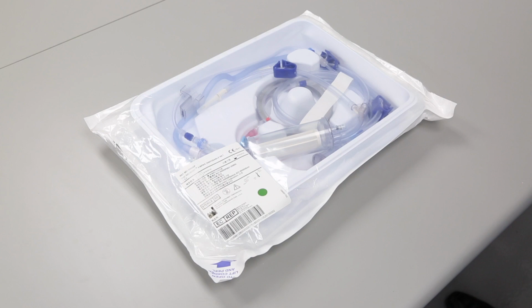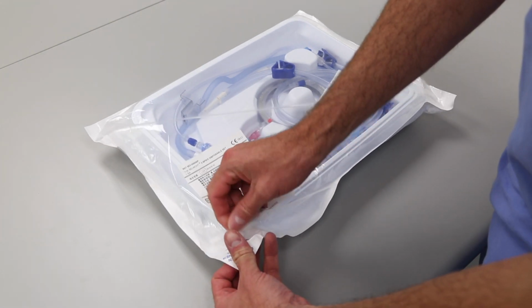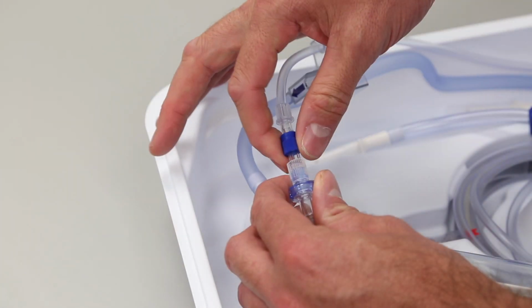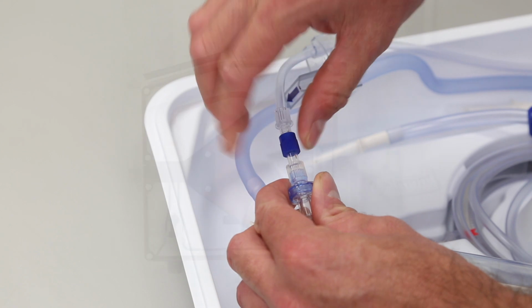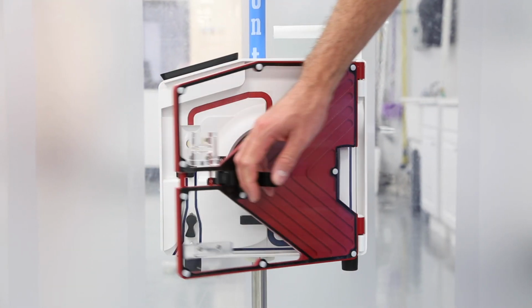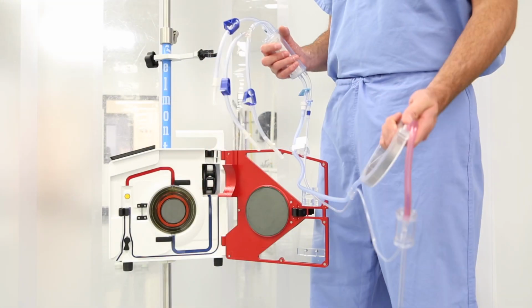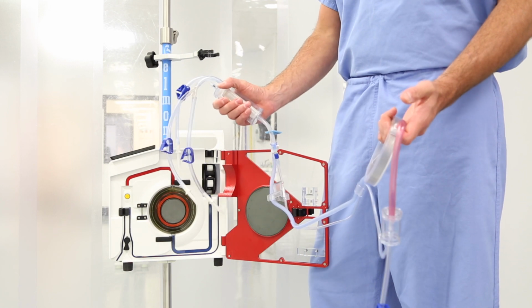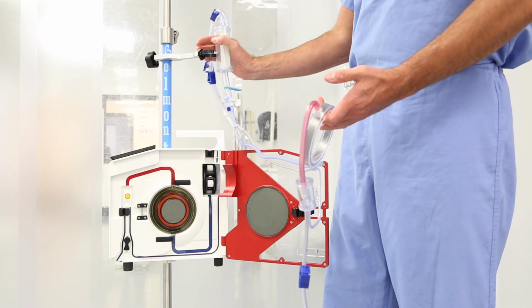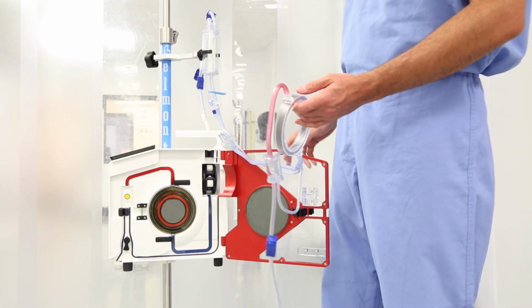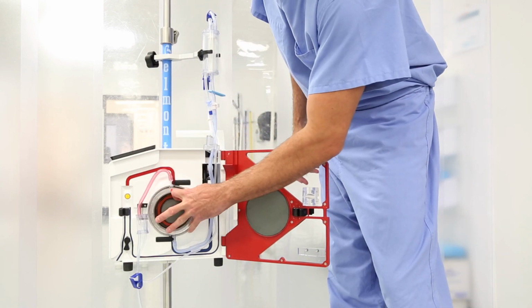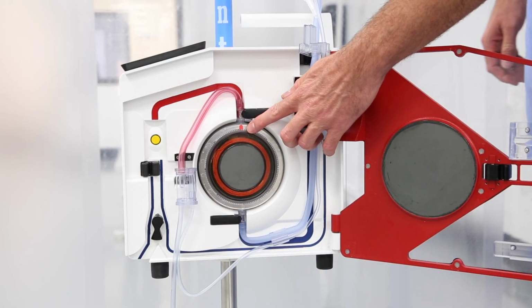The single patient use disposable comes pre-assembled in a sterile container and is color-coded for easy installation. Begin by opening the disposable package and tightening the two luer locks. Open the door of the unit. Holding the heat exchanger in your left hand and reservoir chamber in your right, snap the reservoir chamber into the holder. Insert the heat exchanger with the red arrow pointing up.